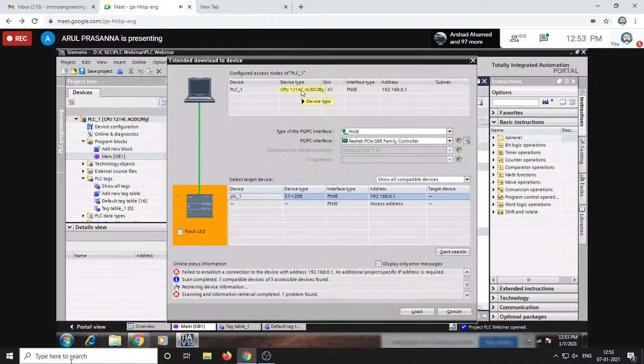Now, if your software PLC device type and your hardware PLC device type are not matching, then you can't download. So that I have confirmed with my hardware PLC before selecting my software PLC with this CPU type, CPU 1214C AC/DC relay, like that.